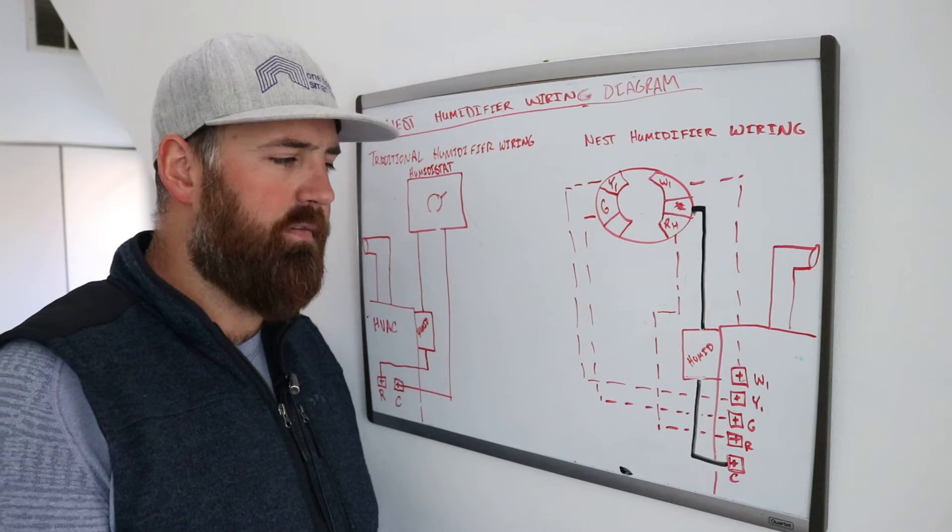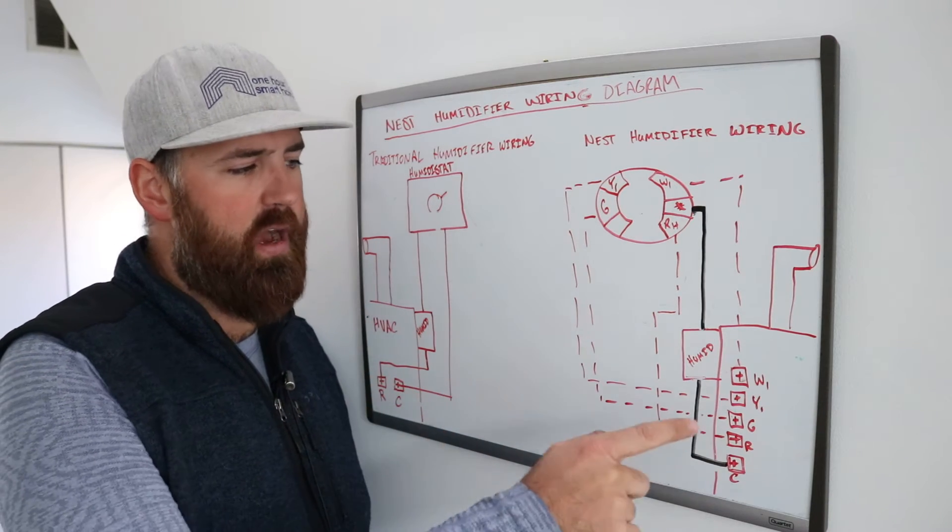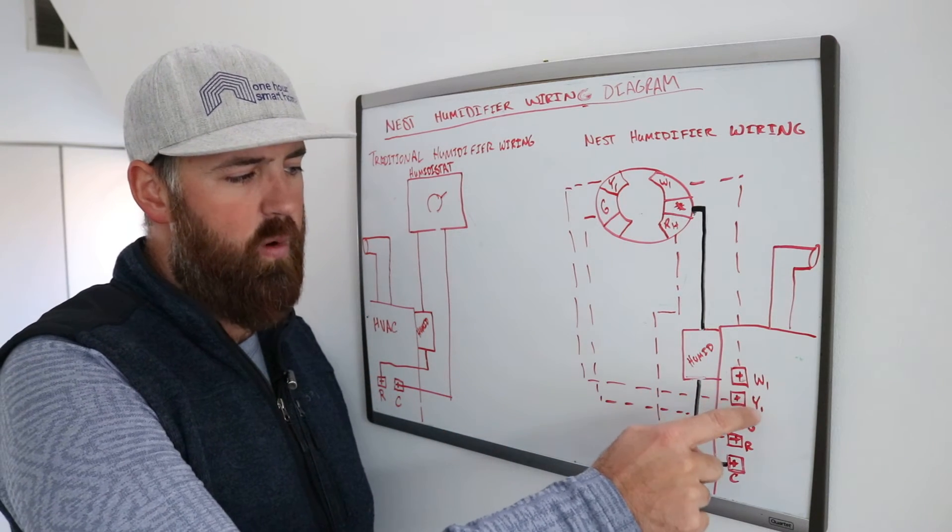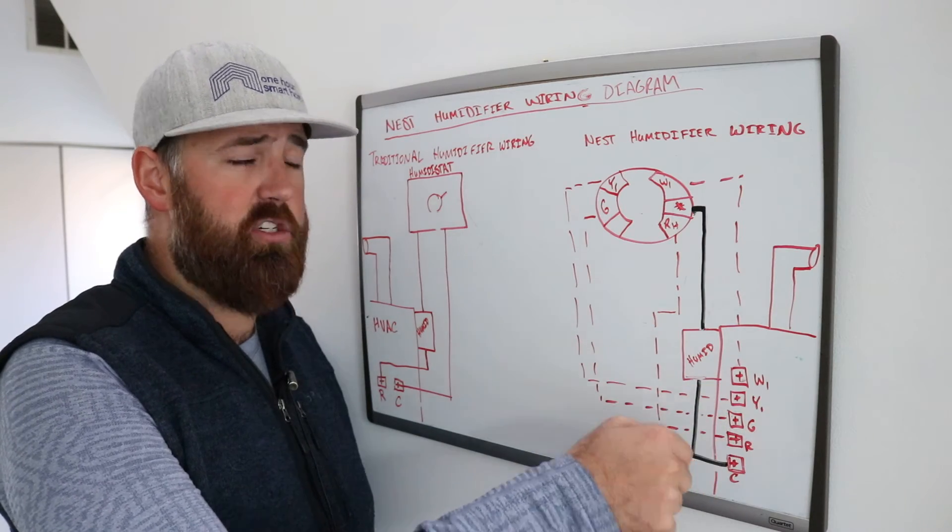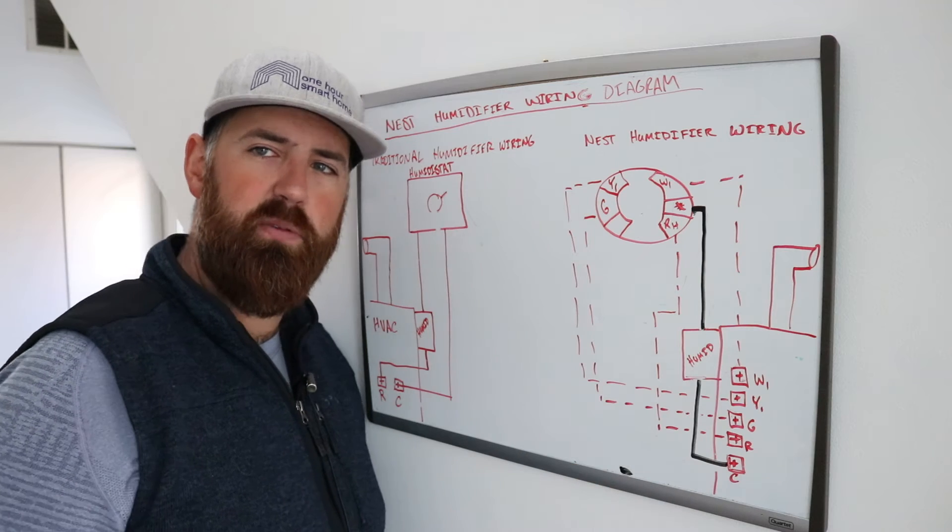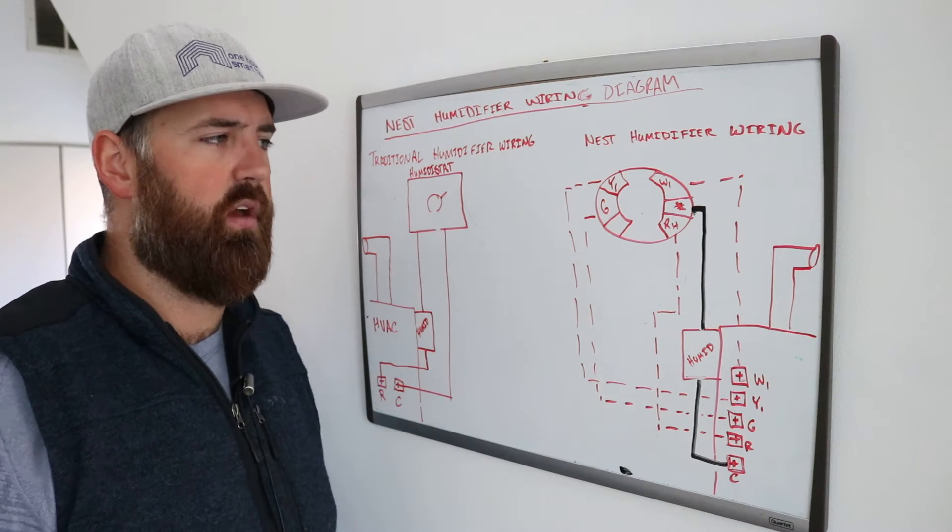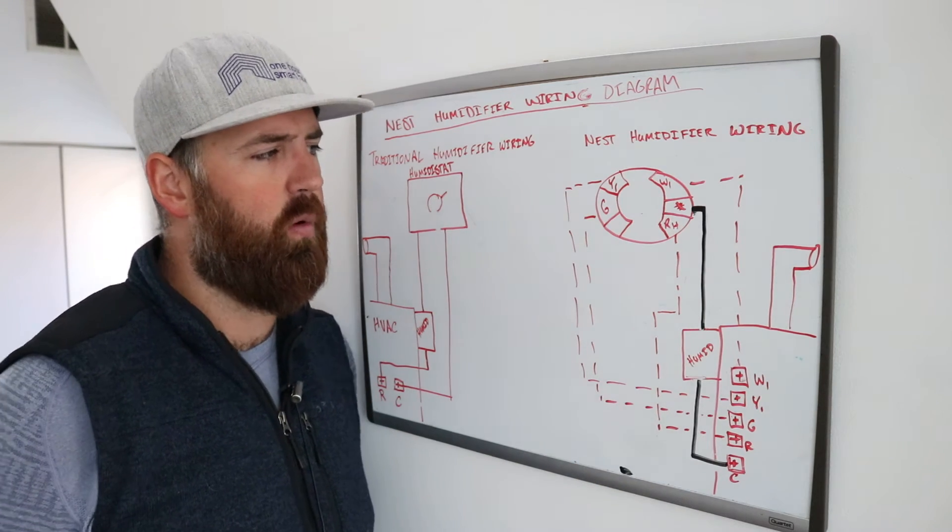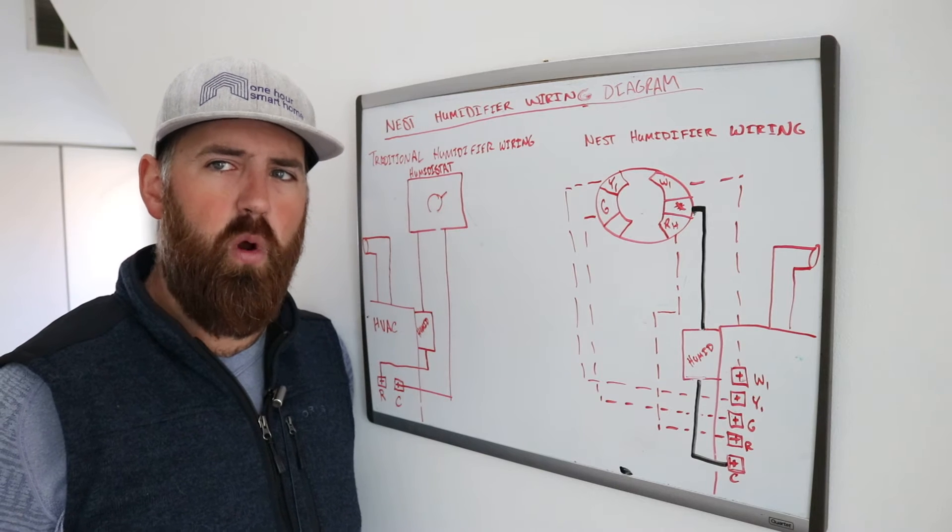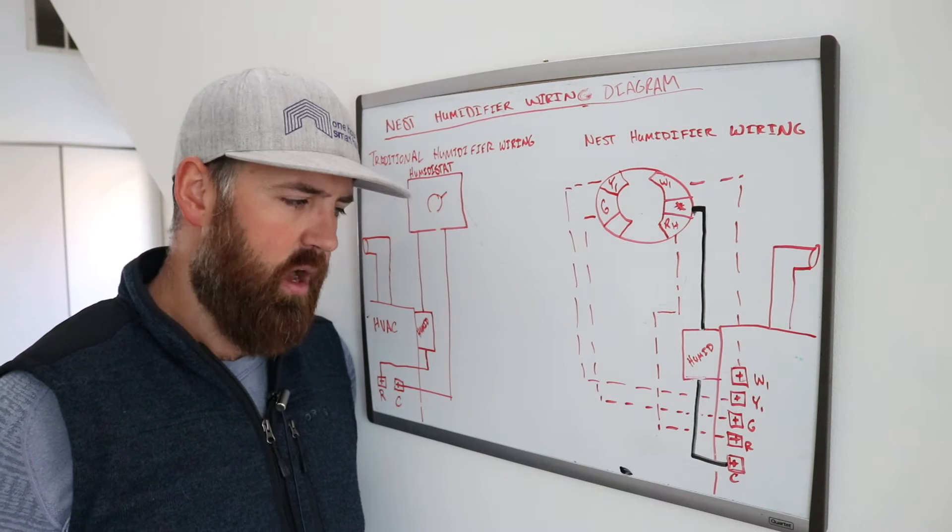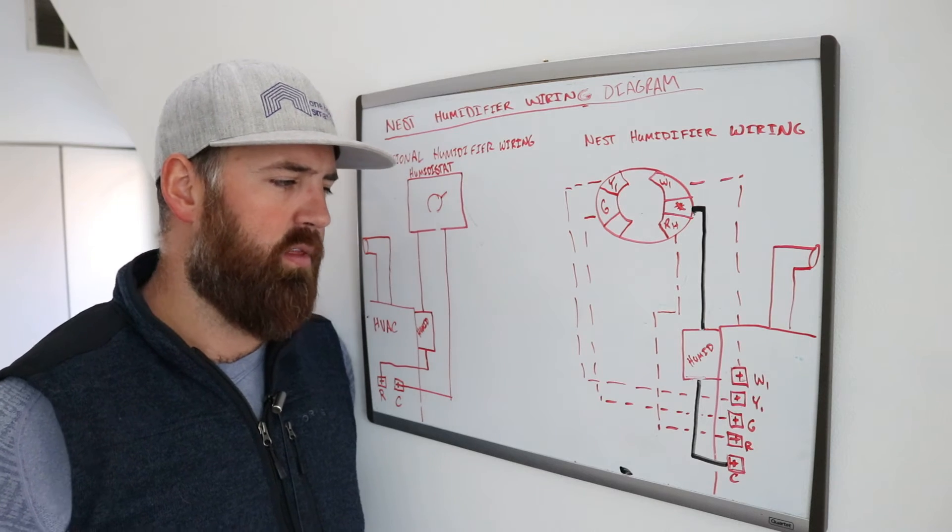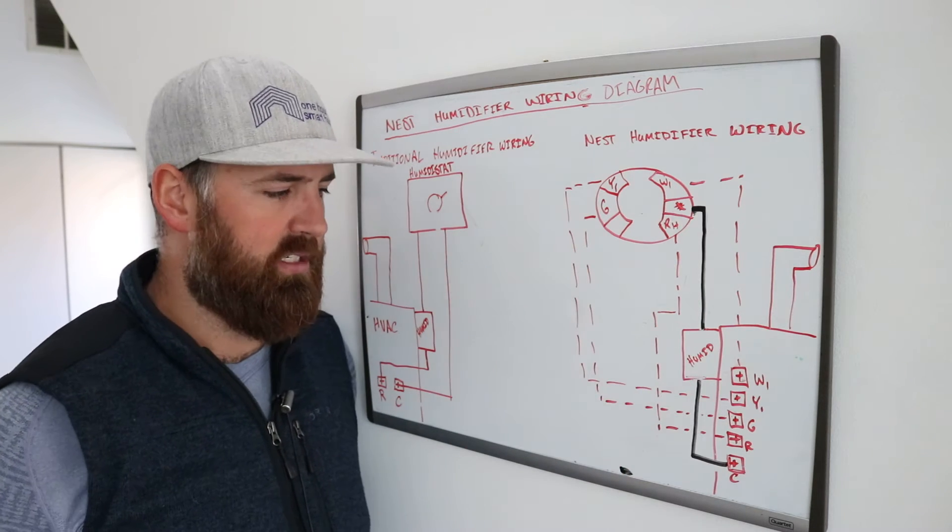So what you've got for a Nest, just typical wiring, you're going to have W1 which is your heat wire, Y1 which is your AC wire, G which is your fan wire and R which is the power wire. Those are just all in dotted lines because they're kind of irrelevant to how the humidistat humidifier works with a Nest but those are what power your Nest and allow it to turn on and off. The R wire is technically the power but all these other ones are just needed for your thermostat to function.